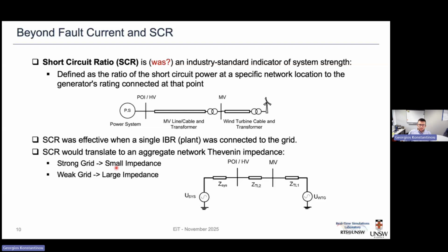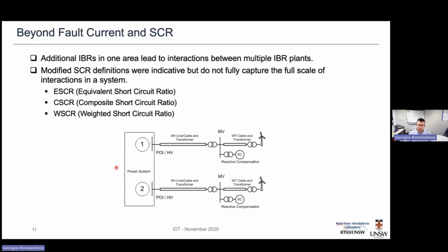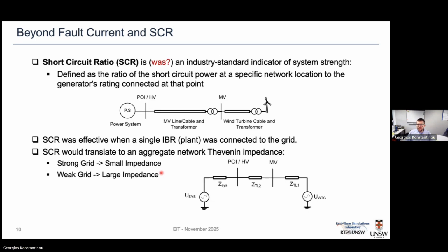But the more renewables and inverter-based resources we connect into the system, the less useful these definitions become in telling the whole story. There were attempts, when the proportion of inverter-based resources in the system was still much smaller, to redefine this short circuit ratio, looking at what were defined as the equivalent, composite or weighted short circuit ratios. So trying to redefine the way the injections from inverter-based resources to the rest of the network would take place. But again, with a focus on the specific short circuit power at a particular location, and then the definitions based on inverter-based resources.